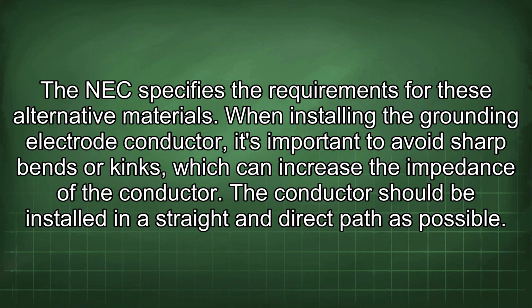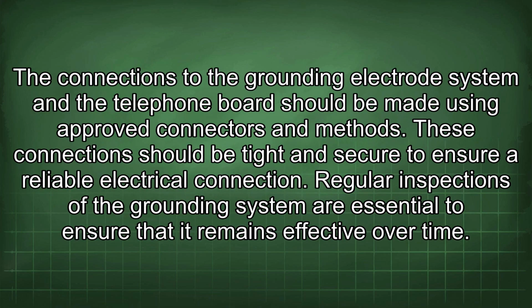When installing the grounding electrode conductor, it's important to avoid sharp bends or kinks which can increase the impedance of the conductor. The conductor should be installed in as straight and direct a path as possible. The connections to the grounding electrode system and the telephone board should be made using approved connectors and methods. These connections should be tight and secure to ensure a reliable electrical connection.